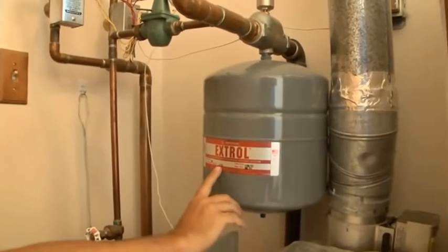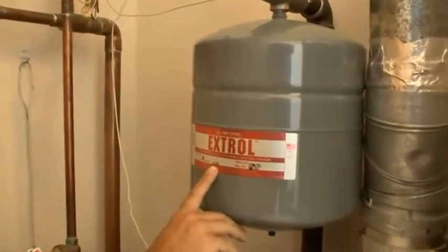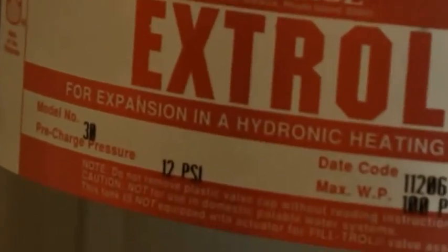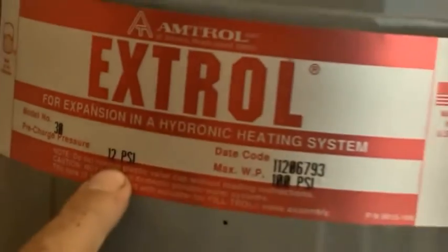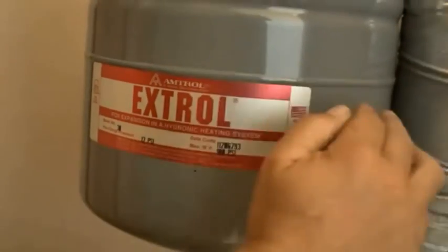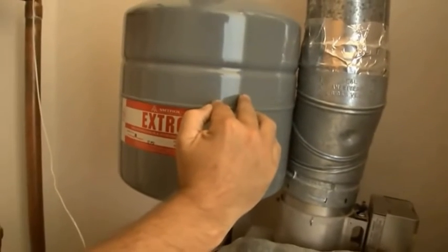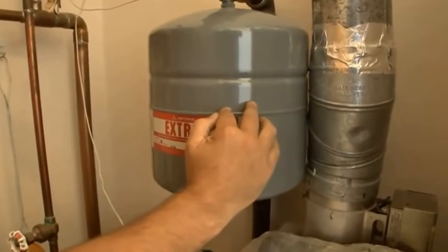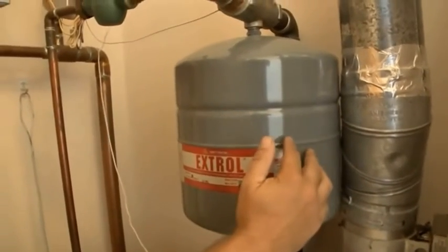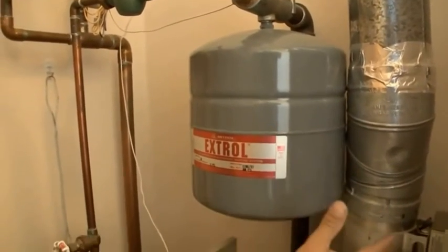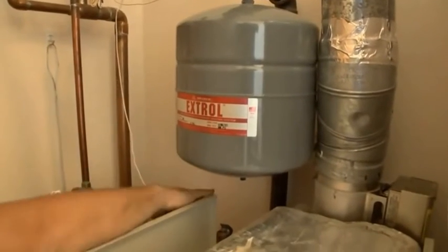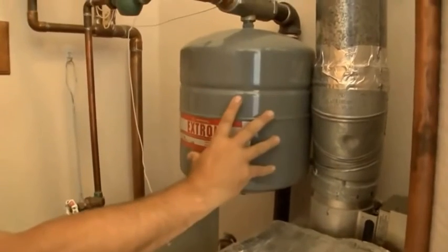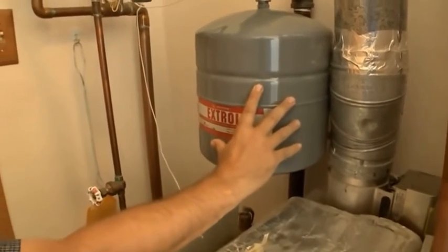Well, what happens is that pressure is no longer 12 psi, it's a higher pressure. And so if you don't even check it before you install this, and you just install it assuming that's correct, now you have a higher pressure expansion tank. And because of that high pressure, it can't absorb as much expansion, and that may cause you to lose water out of your relief valve. Your pressure might get too high. So it's critical to check the pressure on these before you install them.